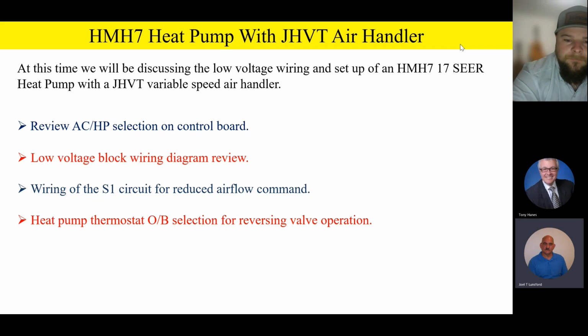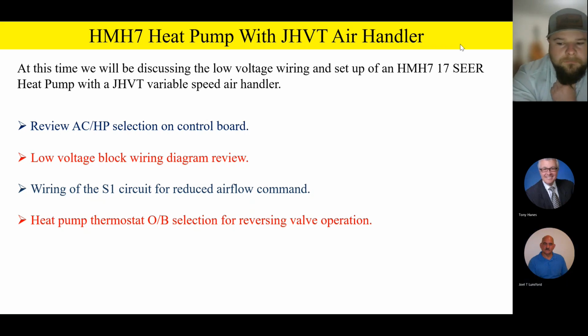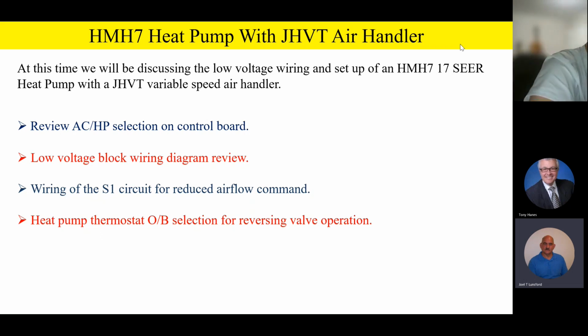So be sure and pull that hard common wire all the way through. In addition, one other little tidbit to remember is, because you're not using the relay kit with the JHVT air handler, the contractor is going to have to provide a field installed biflow filter dryer on the liquid line. So please remember that if you're not using that little 001 kit like we do on the other product, they're going to have to provide a field installed filter dryer.